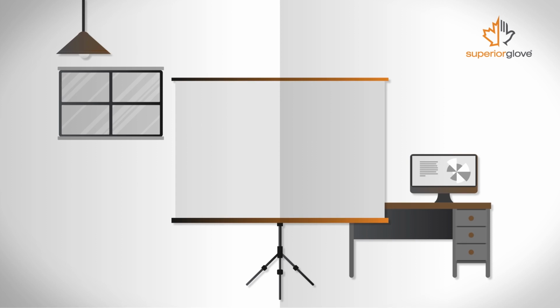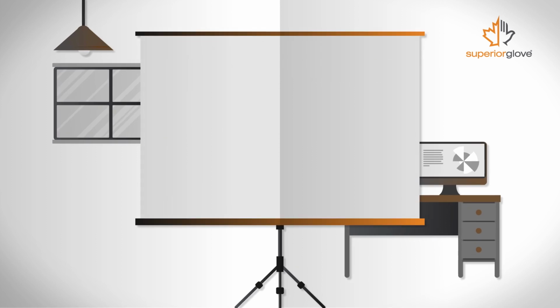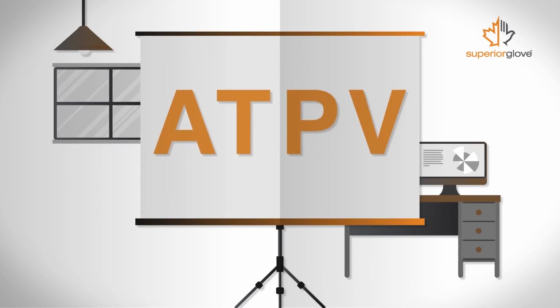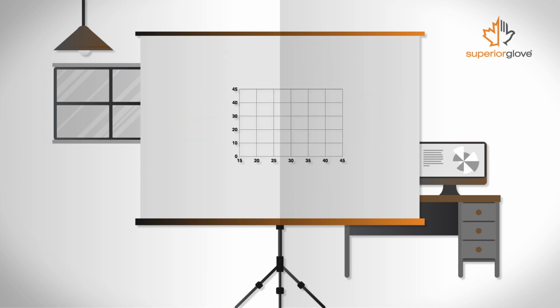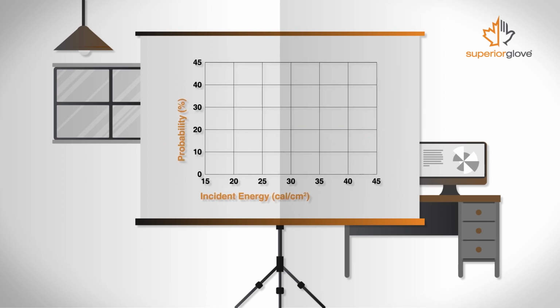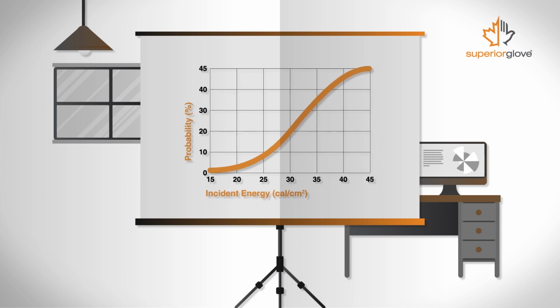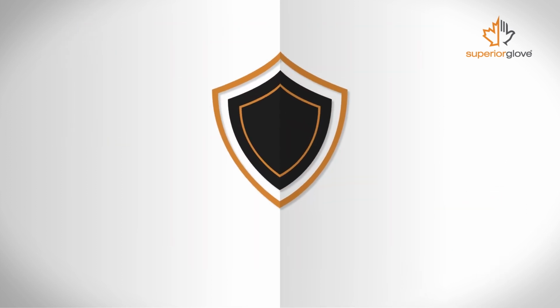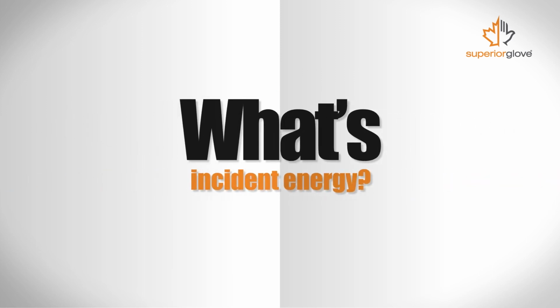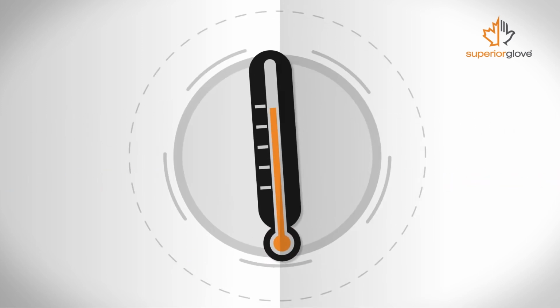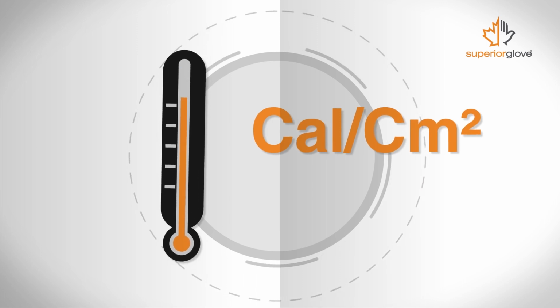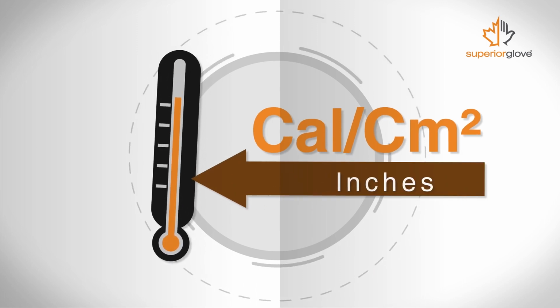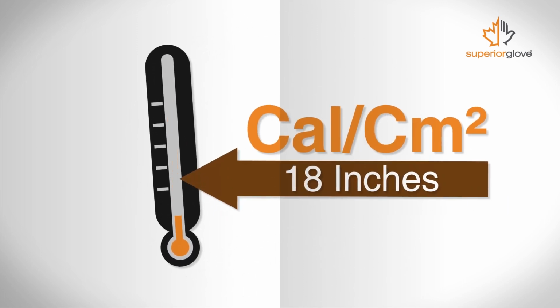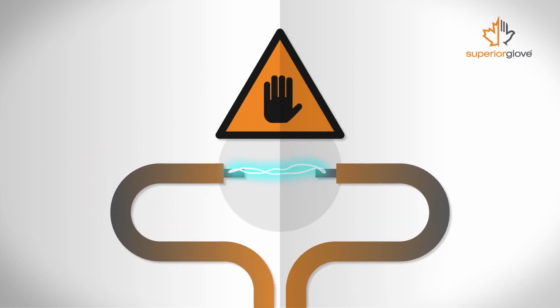When choosing arc rated gloves, you need to look at the glove's arc thermal performance value, ATPV. ATPV is the incident energy needed to cause a second-degree burn. So, the higher the ATPV measurement, the more protective that glove will be. It's the temperature produced in calories per centimeter squared at a certain distance, usually 18 inches, from an arc flash. It's called incident energy because it's energy that isn't supposed to be released.